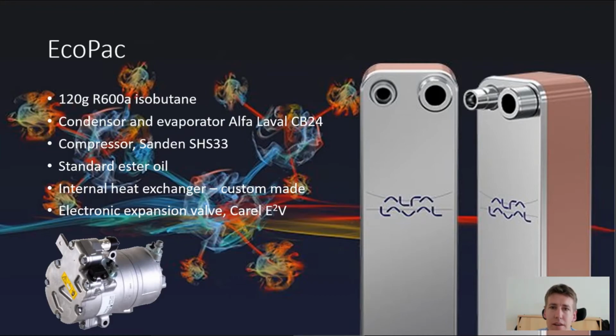So far we're using standard ester oil, so nothing special about the oil. So all these components are industrial and can be found on the market today. What we still are struggling with, or that needs a bit of work, is the internal heat exchanger that we're using. Here we're using a custom made or a handmade expansion heat exchanger, and electronic expansion valve is a industry standard expansion valve, and it's working great, but we do have a few problems. One of the problems is that the compressor is able to run over such a large range, meaning that we can't really use one expansion valve to control the whole range.